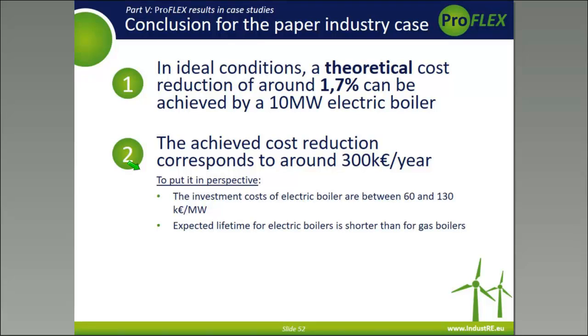To put that in perspective, the values are compared here with the investment cost for that boiler. The 1.7% mentioned corresponds roughly to 300,000 euro savings per year. The investment cost for an electric boiler is about 60 to 130,000 euro per megawatt, so in theory a payback time of about 2 to 3 years would be possible if the 1.7% could be reached.